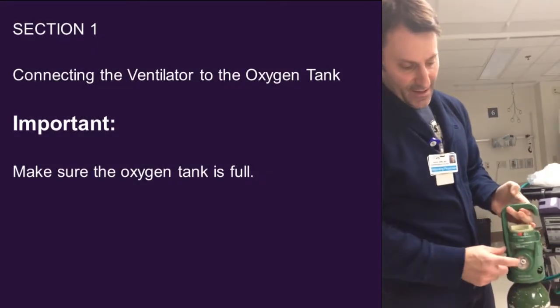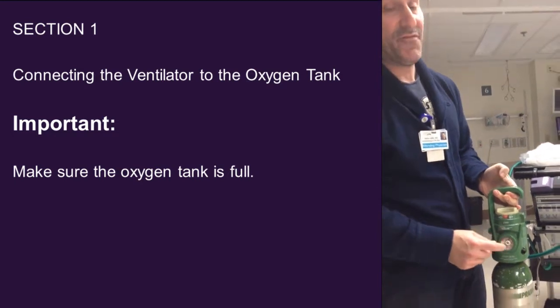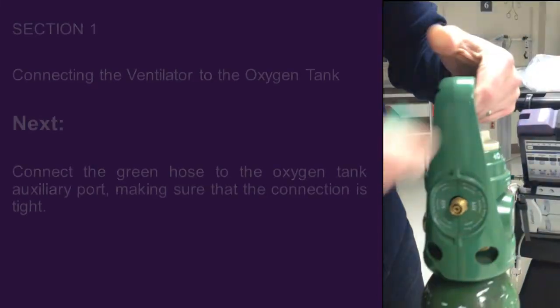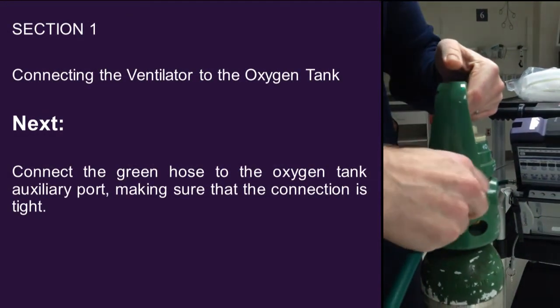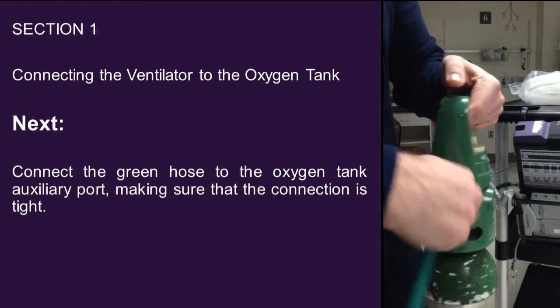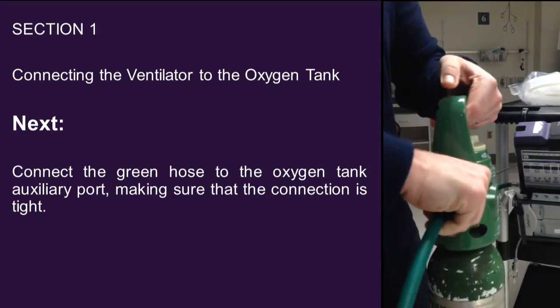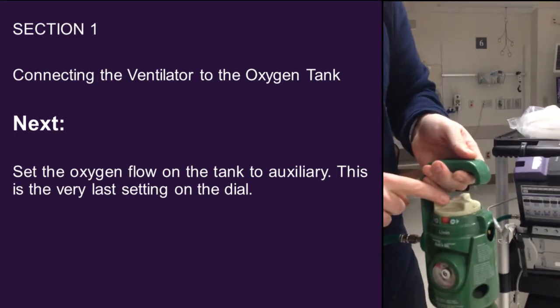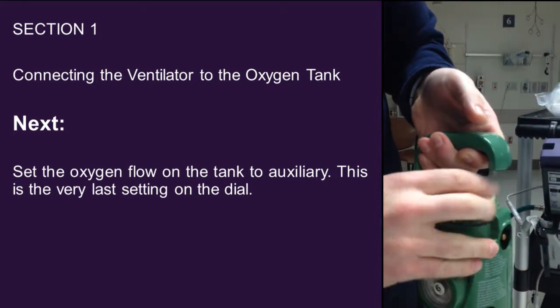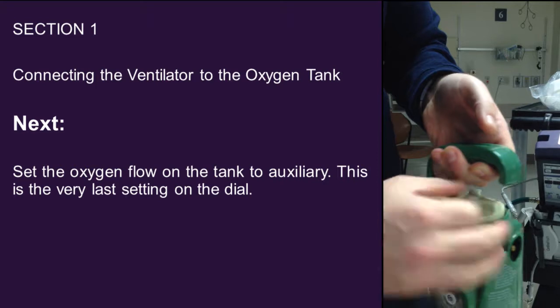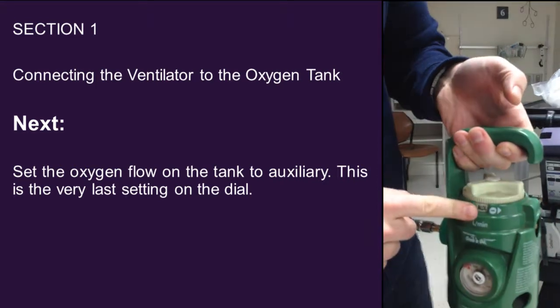So the first step, hook up the ventilator to the oxygen tank. Always want to make sure that you have a tank that is full. This is the gas line. So this is the auxiliary port on the oxygen tank. This then gets simply screwed into place. Make sure that it is nice and tight. Then the setting needs to be turned to auxiliary. So you keep turning. It's the very last setting.